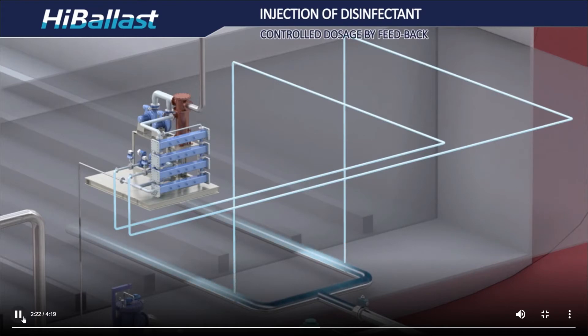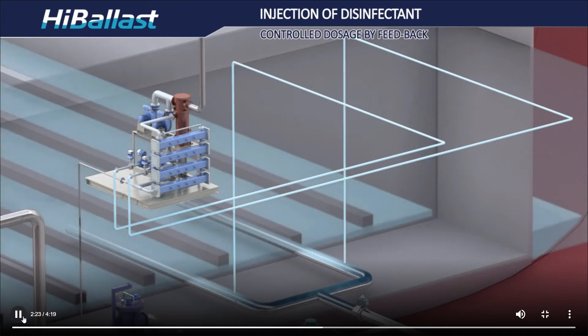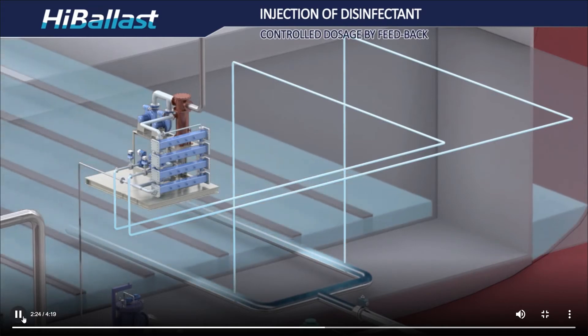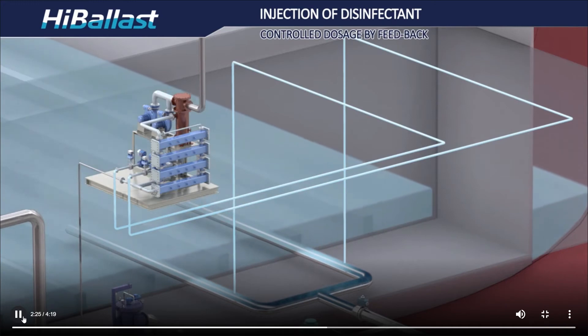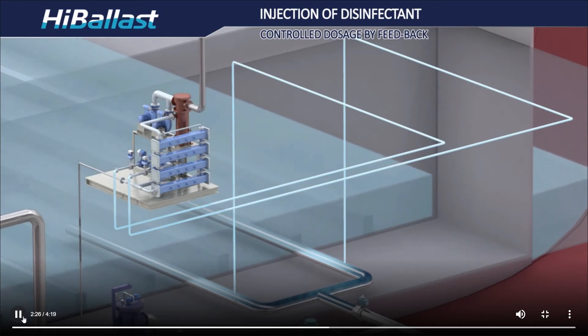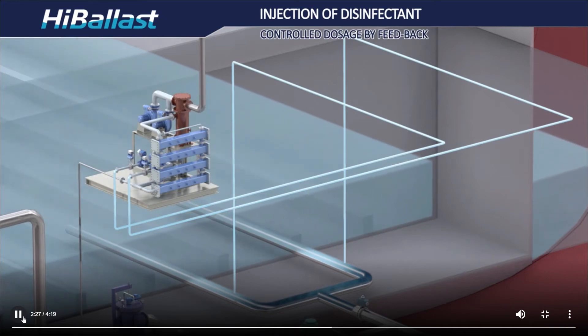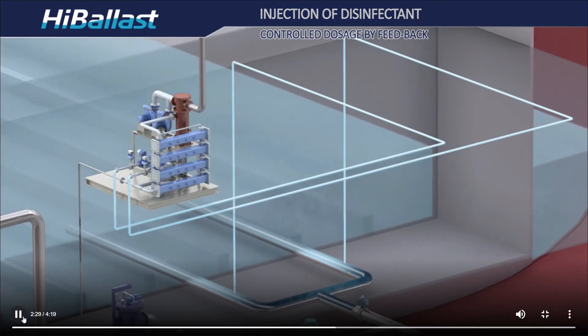The hypochlorite solution, a disinfectant, is injected into the main ballast line and then the sterilization process begins. The dosage of disinfectant is controlled by a feedback loop of continuous TRO measurement and a flow control valve to meet the target dose.